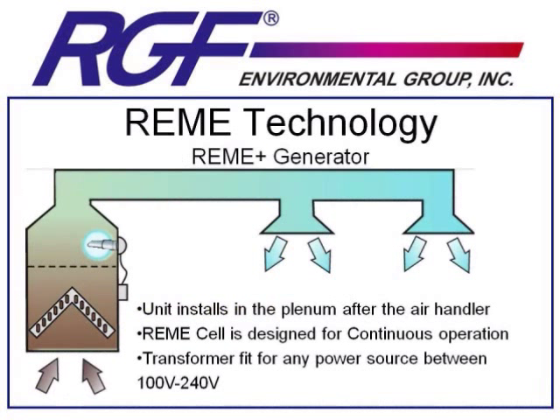A REME system installs very much like a PHI system. You drill a 3¼-inch hole in the supply plenum and mount the unit — it comes with a seal and a gasket. The REME cell is designed for 24/7 continuous operation, and the transformer will take any power source between 100 and 240 volts. It comes with a standard 110 outlet on the end; you can either plug it in or cut it and direct wire it into your air conditioning system.